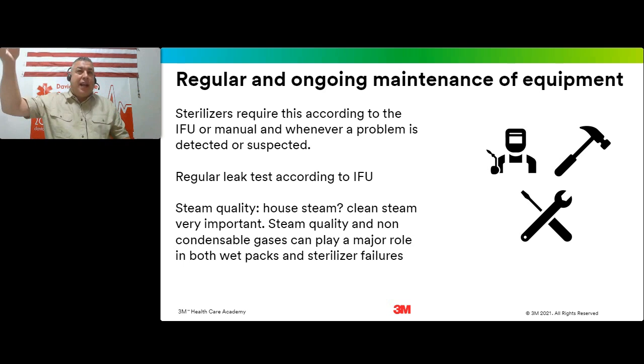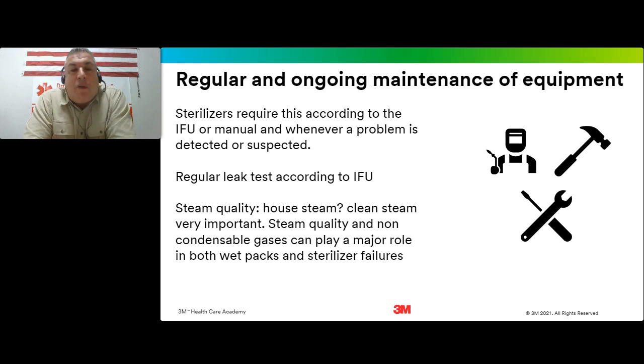And that's a setting within the autoclave that looks to see, does its own built-in leak test. There's been a lot of questions around that lately. And of course, what are the answers? You go to the IFU. The sterilizer manufacturer will tell you when and how you should do that. Steam quality - huge. A lot of us use house steam, we use steam from the boiler plant.